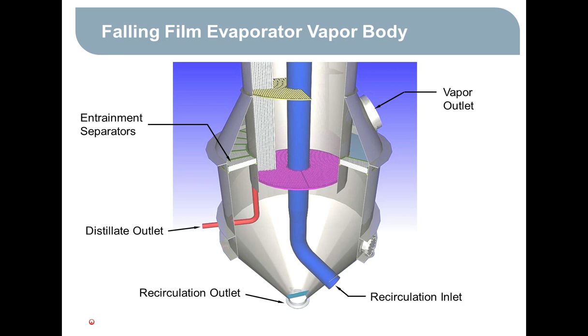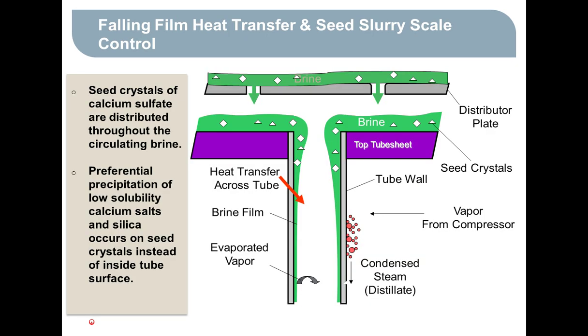So on the individual tubes, this will give you a little idea of what's going on the tube surface itself. You can see at the very top is the distribution plate, and that brine falls through the holes in the perforated distribution plate onto the top tube sheet. And so there's a level of liquid, it's a fairly thin level of liquid that sits on the top tube sheet. And that brine then flows down the inside wall of the tube around the entire circumference.